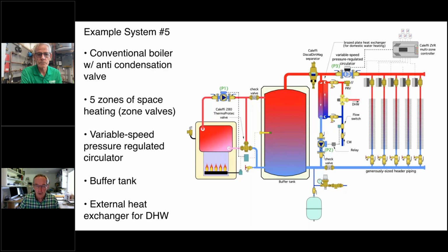This is an external heat exchanger for domestic water heating. Basically, what happens here is when you draw hot water at a fixture, of course, cold water has to come in to replace it. It will trip a flow switch at about 0.7 of a gallon per minute flow, and then through a relay, and we've actually done this right through one of these Caleffi relay centers. It's just a relay that isolates the low voltage circuit from the flow switch to the line voltage to run the circulator.